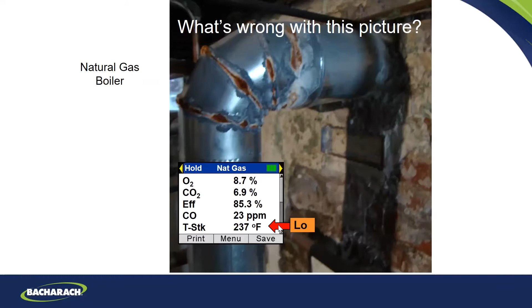Okay, so it's under fired. So this unit was under fired. The problem with this unit also is where you're going to get a lot of this condensation. This house was built in the south side of Pittsburgh, and the house was built in 1902. So it had a big old coal furnace. Okay, so you can see what a clean out here is for the coal furnace. And whoever installed this, it's a hydronic boiler, stuck it into the same old chimney that coal furnace used.